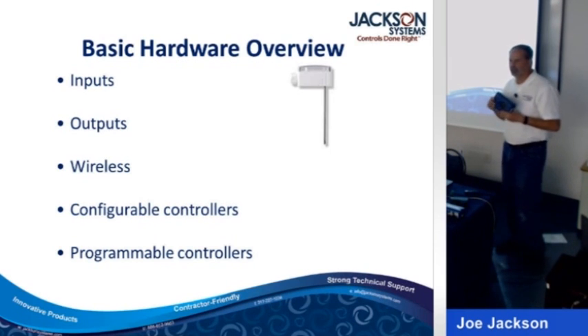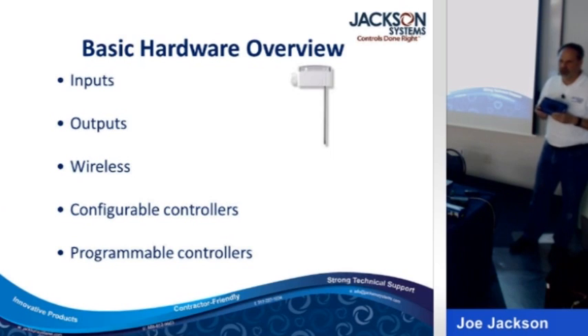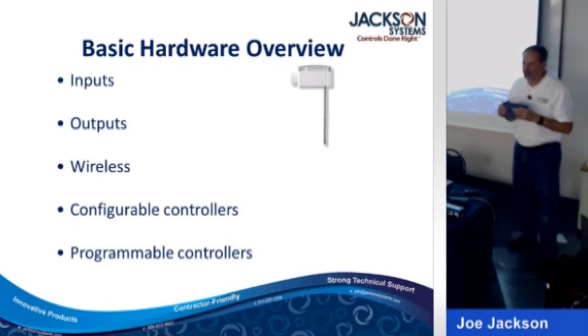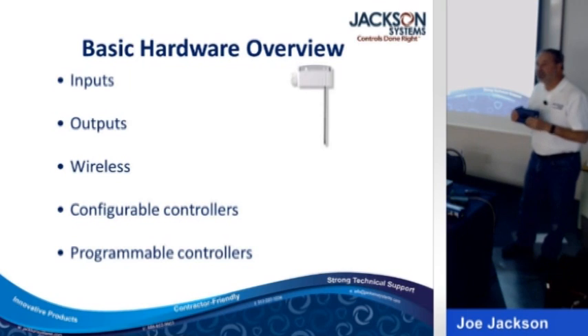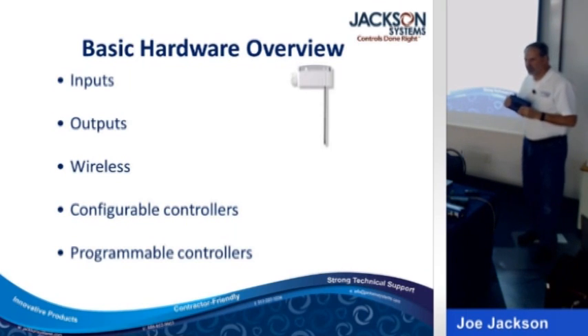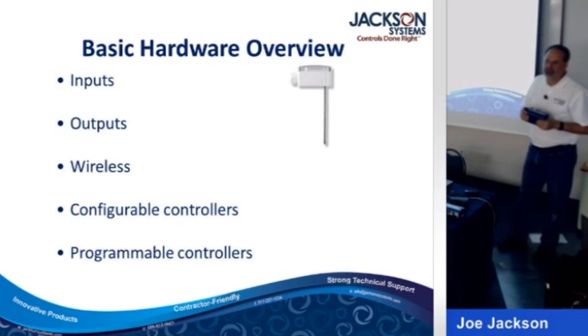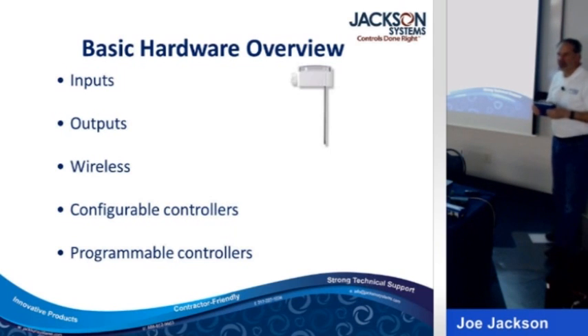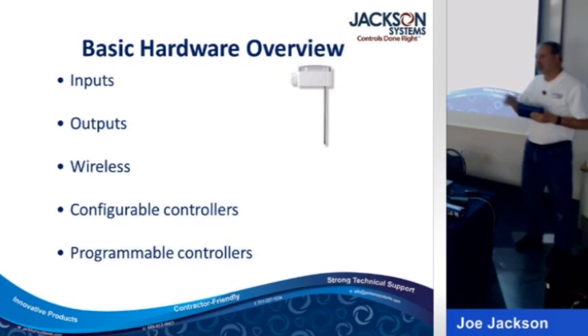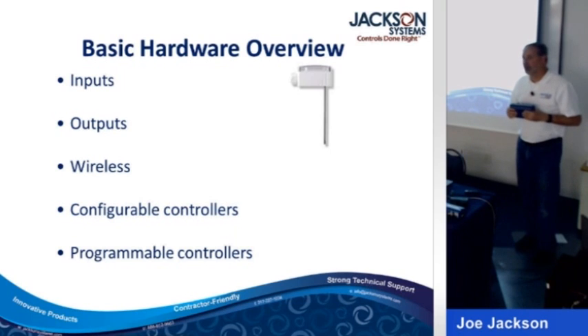If we spent 2 hours together and you had just a little bit of practice after that, anybody in this room could write programs and put them in this. The hard part about this is understanding what the equipment really needs to do. Like at that big chilled water plant we're doing in Nashville, Tennessee, the programming isn't very complicated, but you really have to understand primary, secondary pumping on a chilled water system and what happens to a York chiller if you let water flow through the York chiller when it's not on.